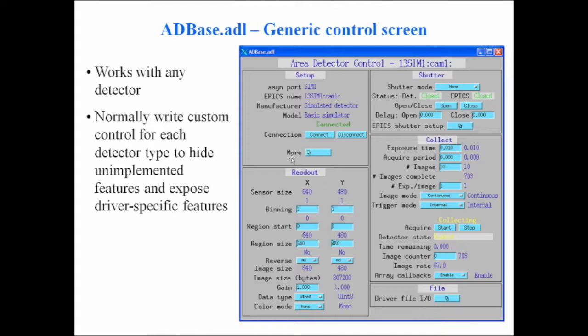Because we have this base class of parameters, we can write generic clients. There's a generic MEDM screen called ADBase.adl, and with this screen you should be able to control any camera. You won't be able to control all the features of any camera, but you could probably make any camera basically work with this screen. Most of the time you wouldn't use it though, since it may display irrelevant parameters and won't display detector-specific unique parameters.